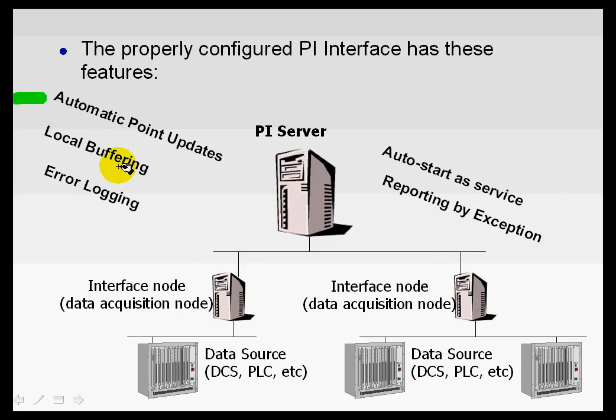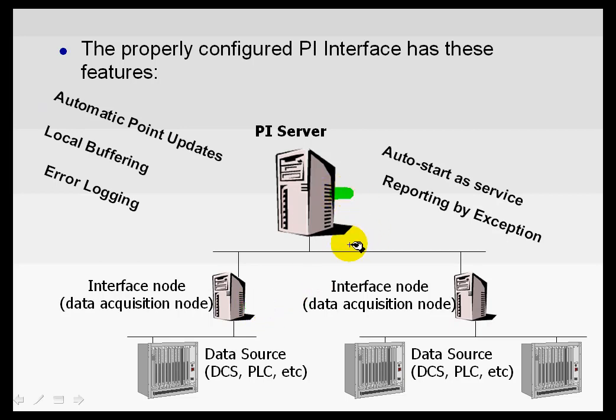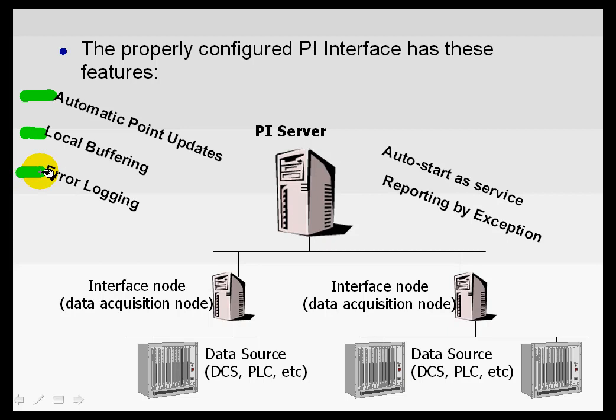First of all, it should do automatic point updates. In other words, when you create a PI Tag on the server, the interfaces affected by that change should automatically propagate that change. For example, if you change from a one-second scan rate to a four-second scan rate, the interface, without having to be stopped and started, should be able to pick that up. So we want automatic point updates. We also want local buffering — buffer data locally if we can't send to the server. And we'd like some kind of error logging to occur.